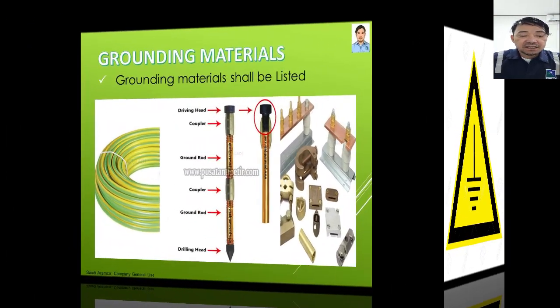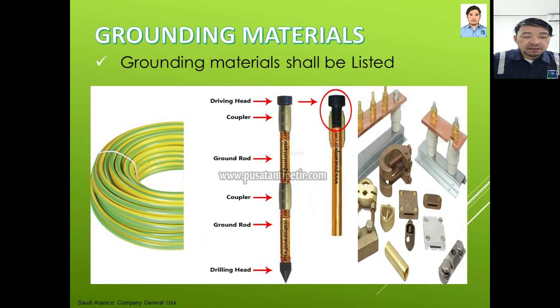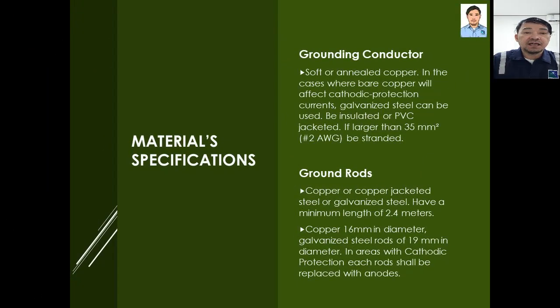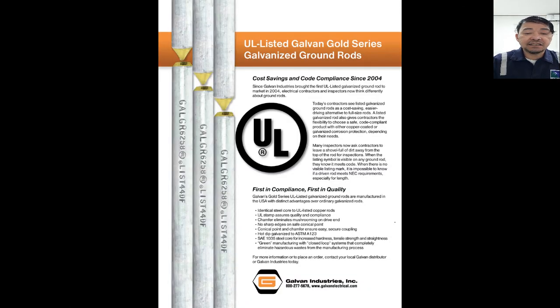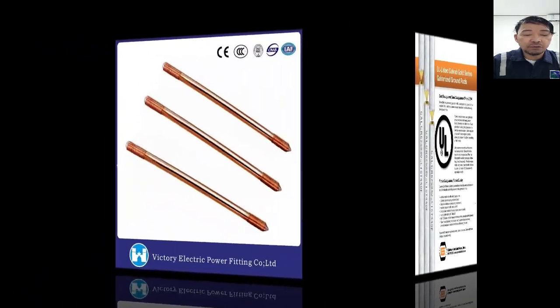Now we will discuss the grounding materials. Materials specification of grounding can be found in section 5 of SAES-P-111. Grounding rod, as per UL-467. UL-467 is the standard for grounding and bonding equipment.